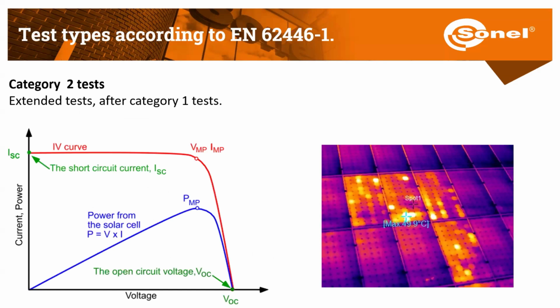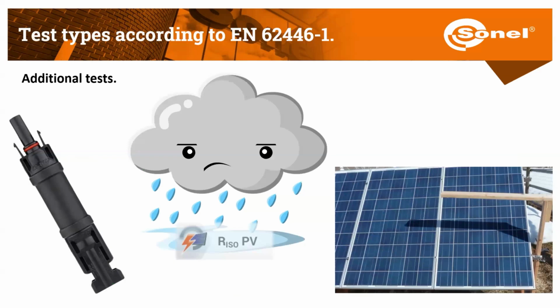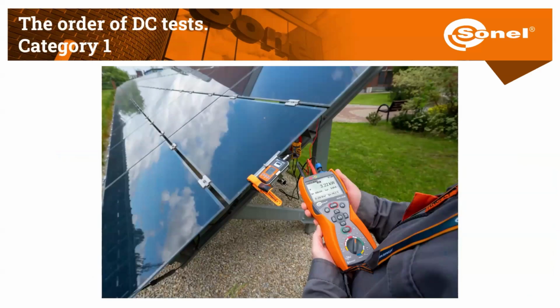Category 2 test, this is the extended test. In addition to the category 1 tests, the following tests can also be applied: current-voltage characteristic, known as the I-V curve, and thermographic test. But these tests should be made if we inspect bigger or the biggest PV systems. Additional tests include voltage to ground, blocking diode test if it is used, wet insulation test, and shade evaluating.